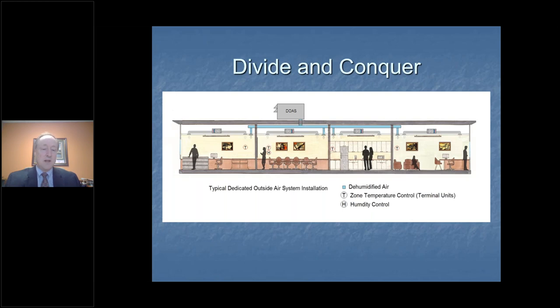The varying factor is what's coming in from outside. So if I can negate the effect of the ups and downs of the humidity and the temperature in some type of dedicated outdoor air unit, and then deliver that air into my space at somewhat of a space neutral temperature, then I can just let all of my fan coil units, or whatever else I might have conditioning my space, be driven off of a thermostat in each one of those rooms. But I've got to have a humidistat somewhere driving the operation of the dedicated outdoor air system. So I'm a big proponent of that.